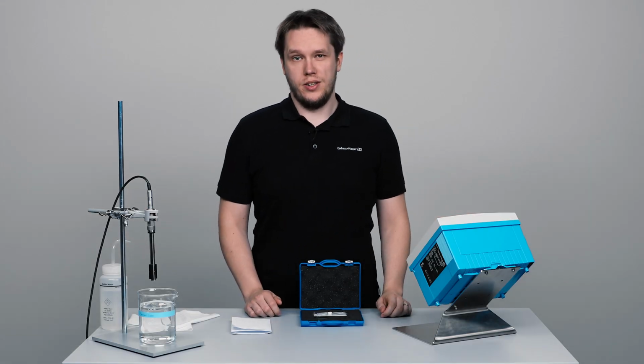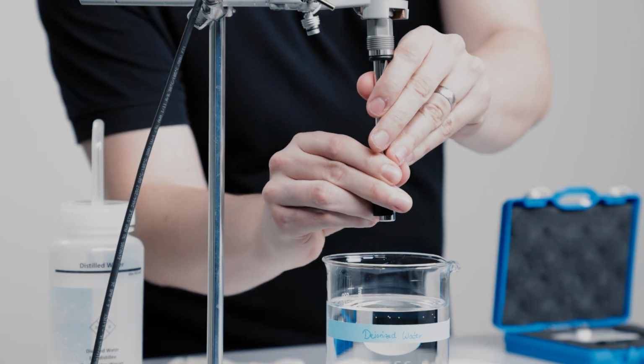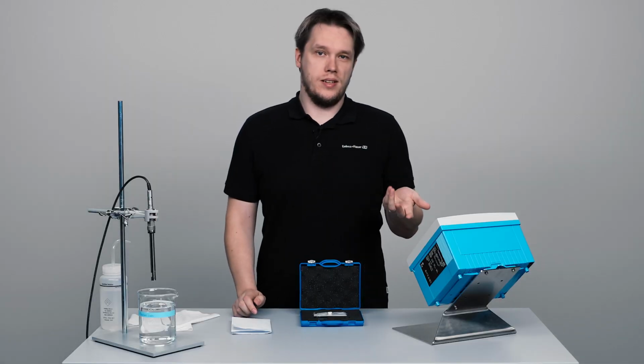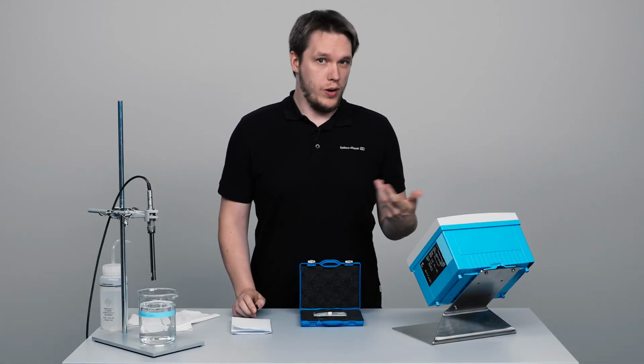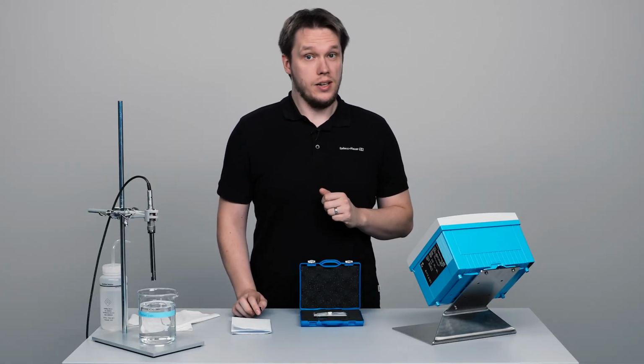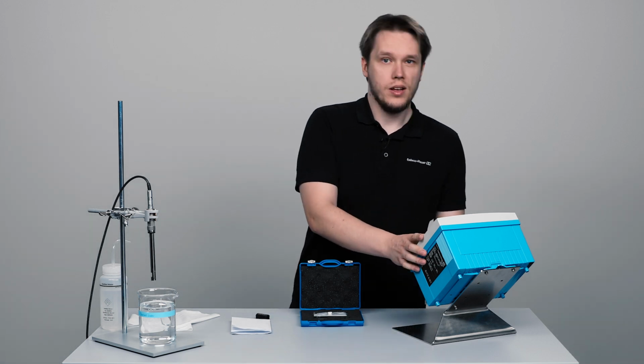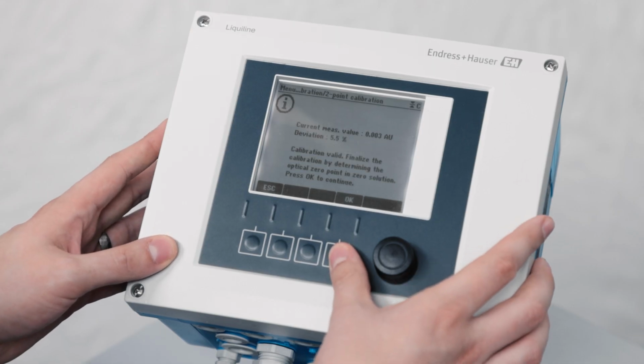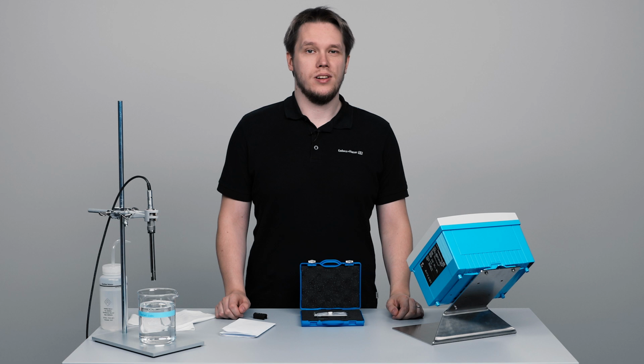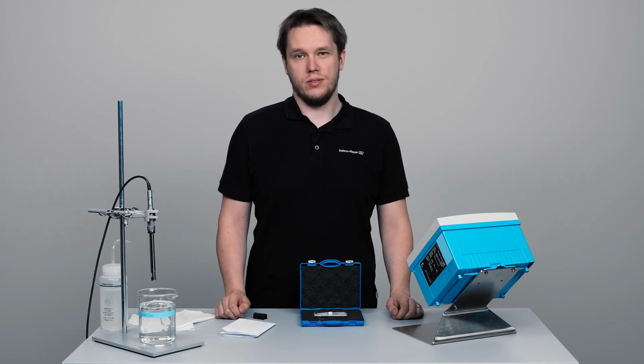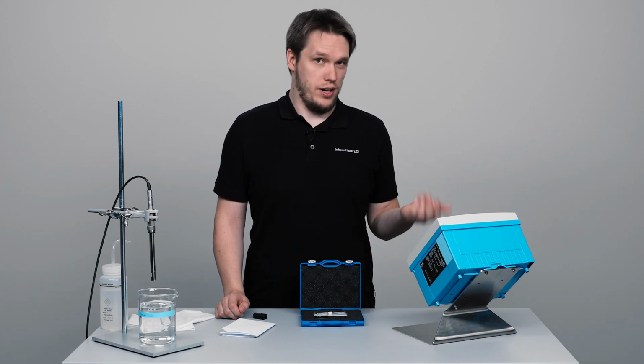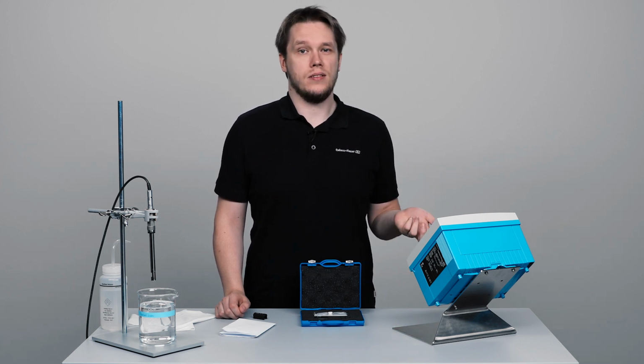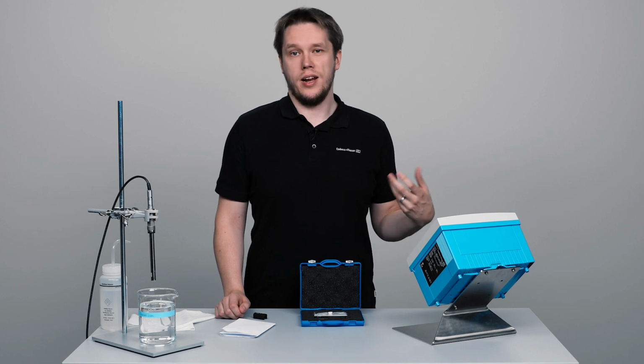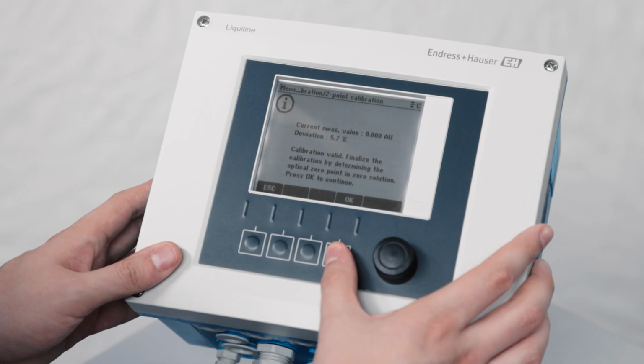Then remove the verification filter and protect the sensor against disturbing light and wait for the signal to get stable in air. Press OK and finish the two-point calibration. On the last screen, you will get information about the current deviation between the verification filter value and the adjusted calibration curve. According to the calibration certificate, the specified deviation is between 0 and 8.6%. Press OK.